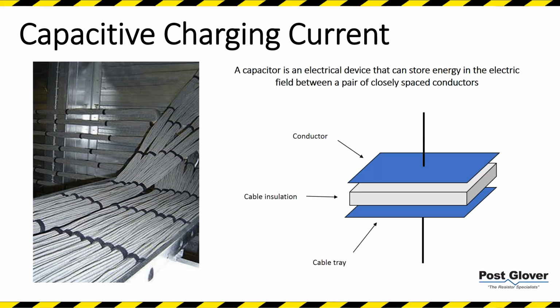So I mentioned it 3 or 4 times. Let's talk about capacitive charging currents. A capacitor is 2 conductors with an insulator in between. You basically have that in any scenario in your system: parallel cables, motor windings, all kinds of different things. You have a small level of capacitance all throughout your system, and that total adds up to your system's capacitance. And your system's capacitance, in terms of line to ground, can compete with your ground fault current. And so you can actually carry current on the capacitive charging current.